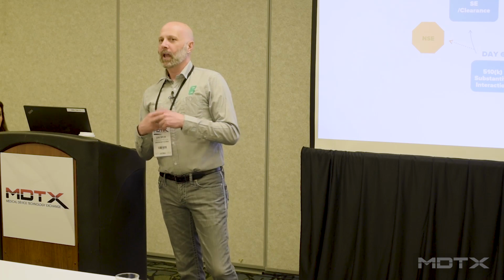understanding what it is that they're asking, because if FDA asked you a question and you knew what they were going to ask, you probably would have provided that information in the submission. So sometimes these questions, they are, like, I worked on a device that was a home use device, electromechanical product, had to go through certain aspects of 60601. And they were asking something about, if it was ambulatory use, and there were some new versions of standards that were draft, they weren't even published yet, that had higher thresholds of testing, and they wanted to know if we had tested that. Not something we anticipated. So usually there are questions that you didn't think of.